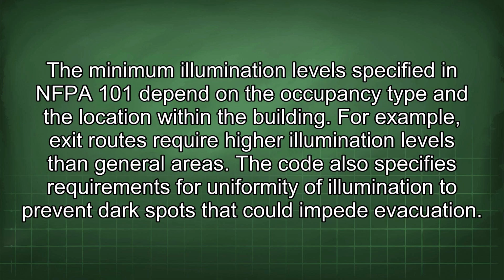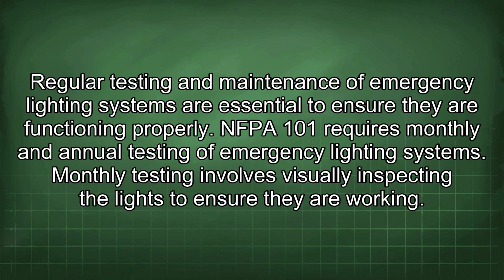The minimum illumination levels specified in NFPA 101 depend on the occupancy type and the location within the building. For example, exit routes require higher illumination levels than general areas. The code also specifies requirements for uniformity of illumination to prevent dark spots that could impede evacuation. Regular testing and maintenance of emergency lighting systems are essential to ensure they are functioning properly.